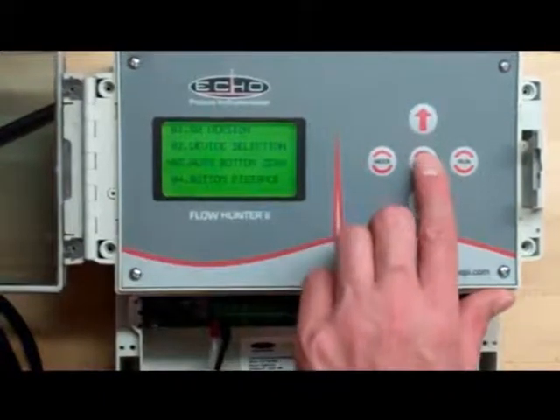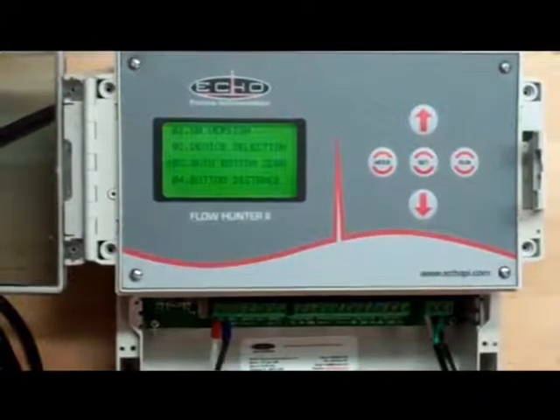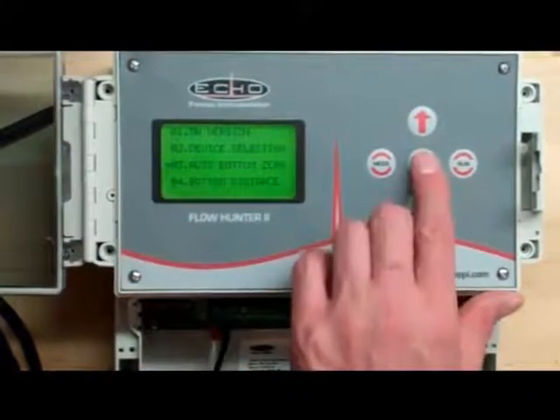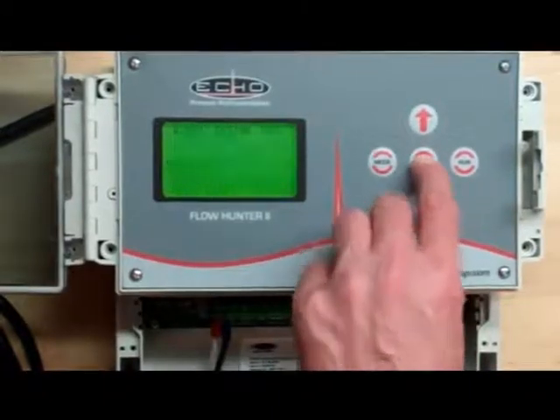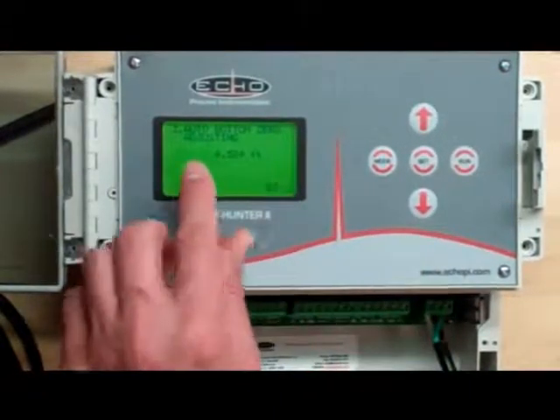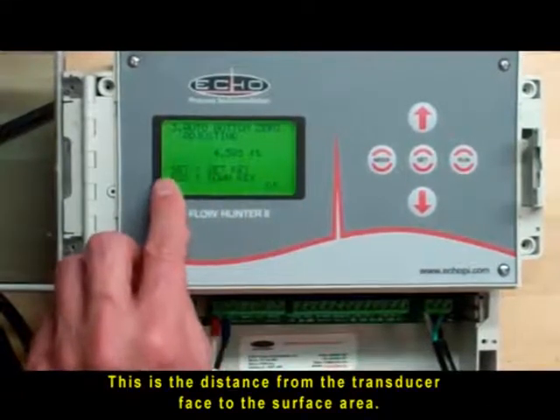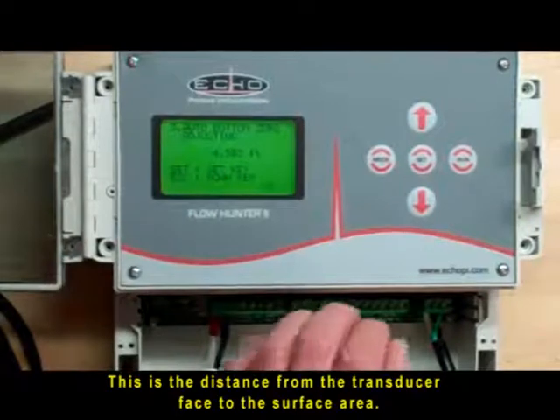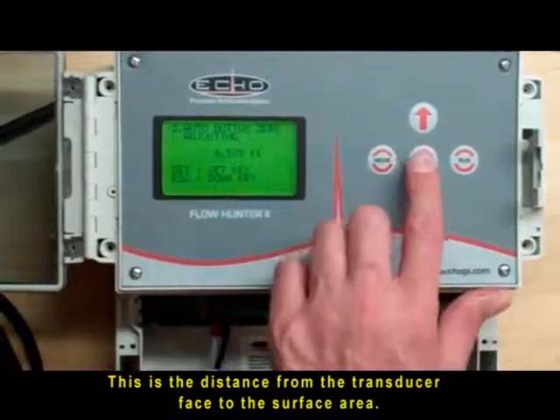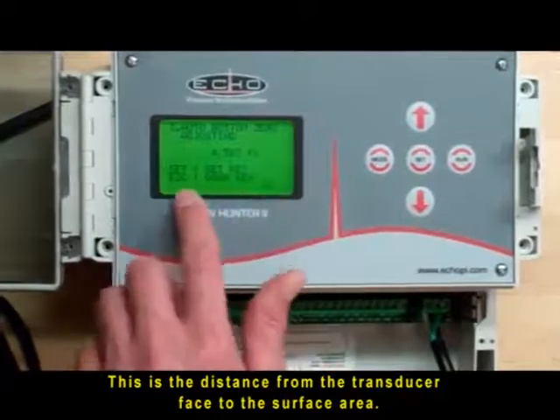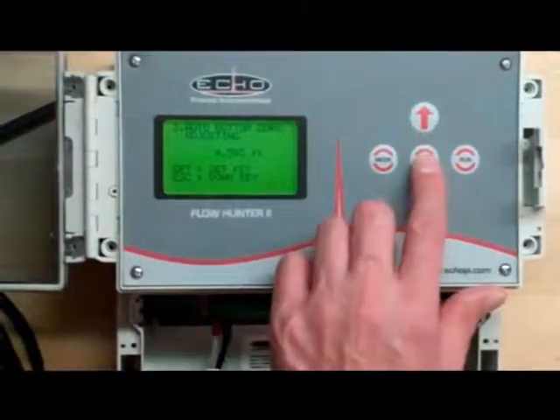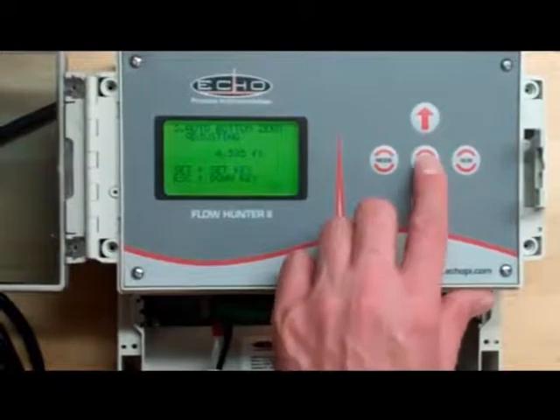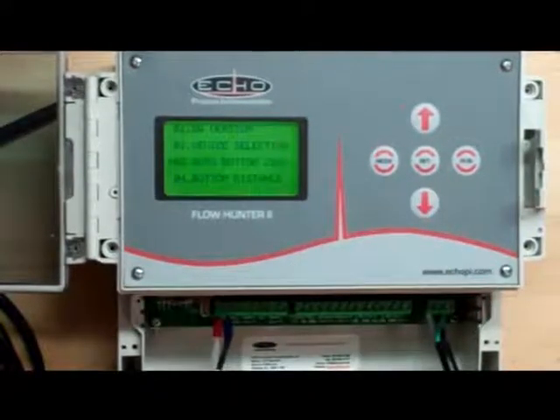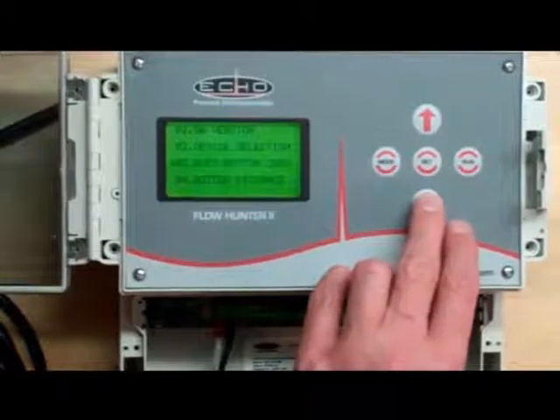We're going to go down to 3, which is your auto bottom 0. If you have the ability to turn your flow off, you can auto detect your empty distance by using this feature. Hit set to go into the menu. Here it's detecting from the transducer face and coming back. At the 0 level it's saying 4.5 feet. Now if I want to select this and set it as my empty distance, I can hit the set button, which will save it, or I hit escape to go down. So let's say I want to do it at 4.5 feet. I just hit set and there it goes. Automatically detects the empty level.